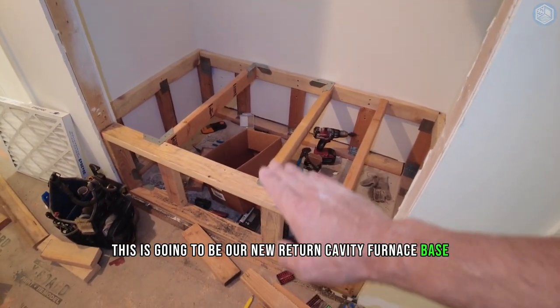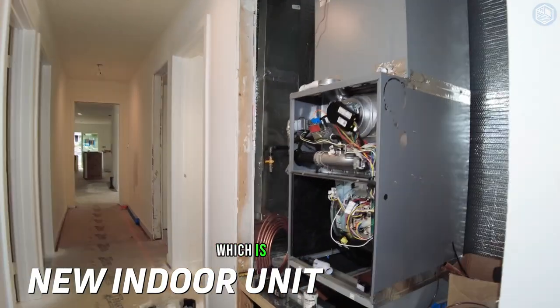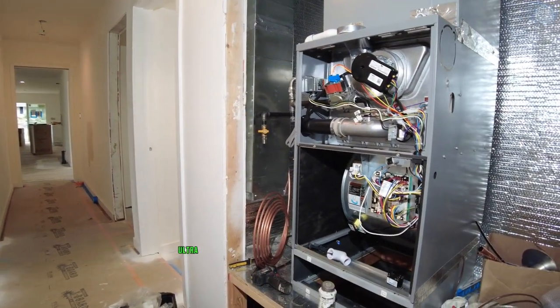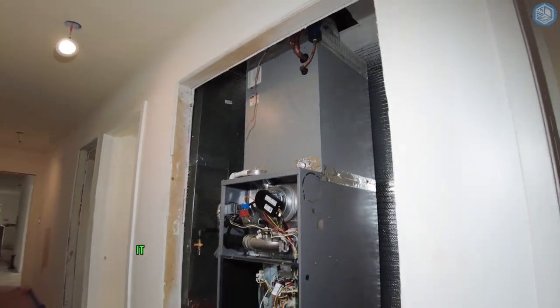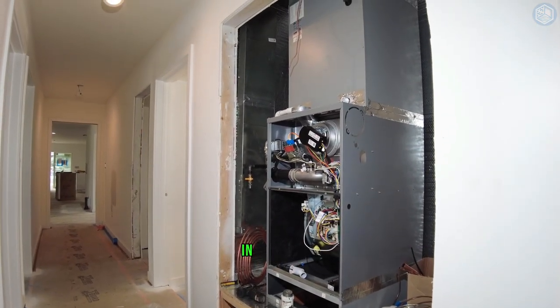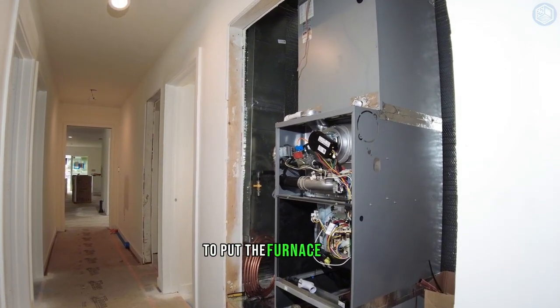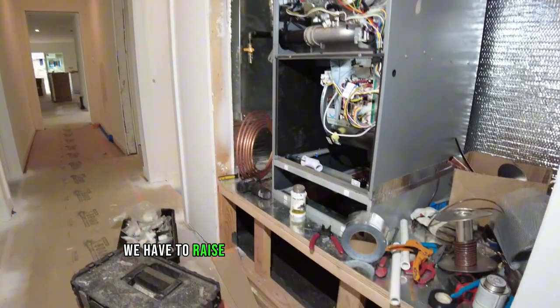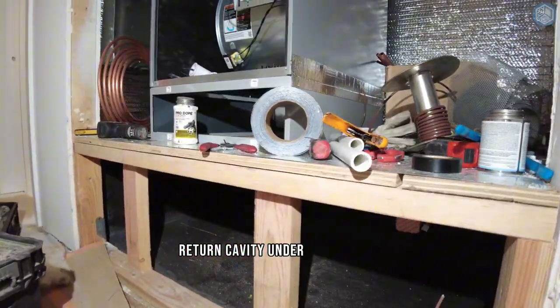Right now we are working on installing the indoor unit, which is a gas furnace, ultra low NOx, and evaporative coil. It's upflow configuration and it goes in the closet in the middle of the house in a hallway. Again, we don't have enough space in the attic. We had to raise the base and build a return plenum, a return cavity under the furnace.